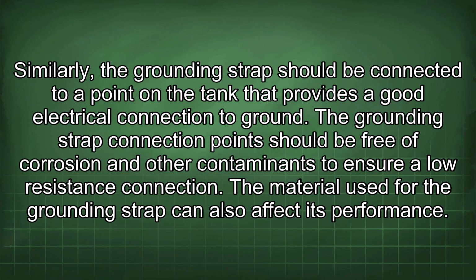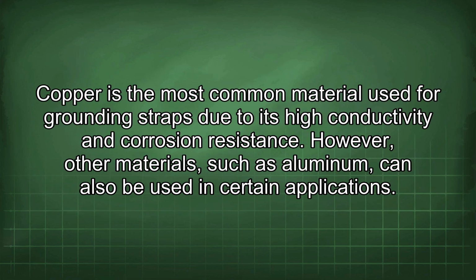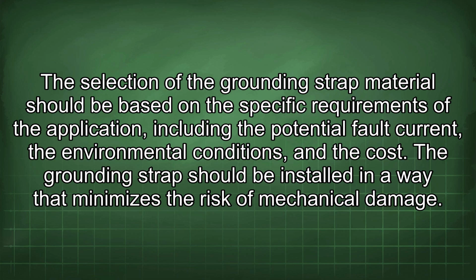The material used for the grounding strap can also affect its performance. Copper is the most common material used for grounding straps due to its high conductivity and corrosion resistance. However, other materials, such as aluminum, can also be used in certain applications. The selection of the grounding strap material should be based on the specific requirements of the application, including the potential fault current, the environmental conditions, and the cost.